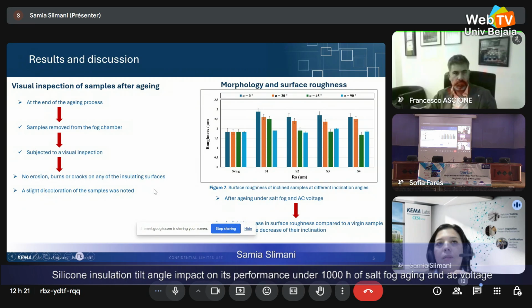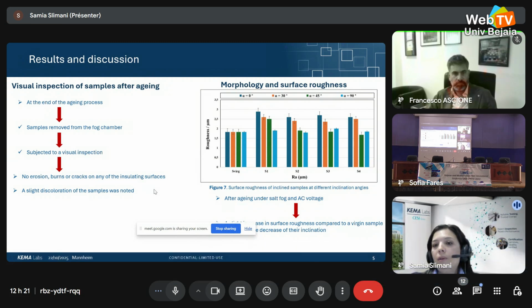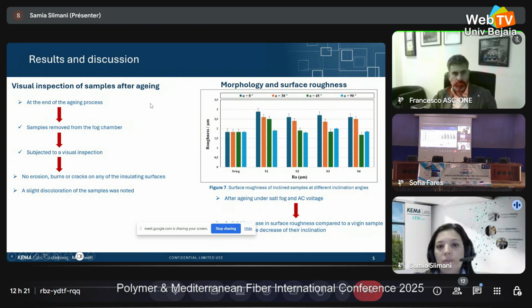The leakage current is recorded using the software NextView 4. It's a very precise software. It can give us around 176,000 measurements in just 1 hour over all the time of exposure to the salt fog and AC voltage.